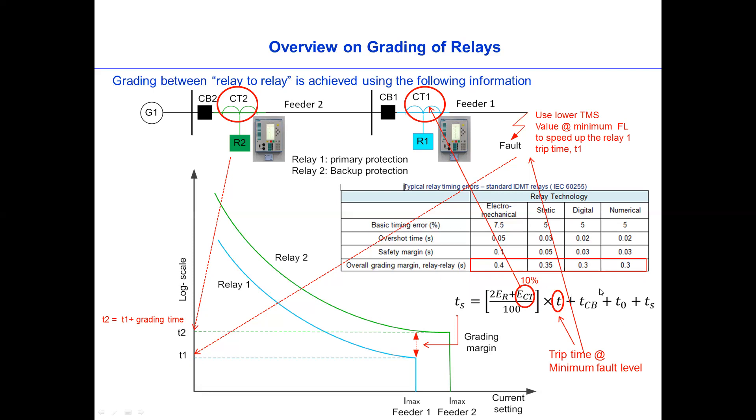And TO is what we have on this one, basically. The parameter depends on the relay technology: the basic timing error, the overshoot time, safety margin. So the TO is the overshoot time, and the TS is the safety margin.